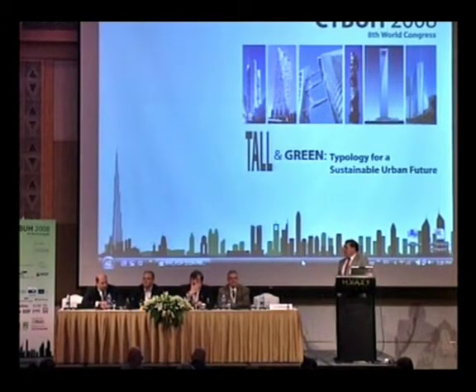So as far as the alternatives go, what I think we have to really do is take a hard look at how we design our sprinkler systems for high-rise buildings. We want to definitely make sure that the sprinkler systems have a high degree of reliability. Perhaps gravity systems or all gravity systems are a thing to consider. Maybe dual riser feeds. I know in the city of Boston, they require dual riser feeds to the sprinkler system, so somebody couldn't necessarily shut off the riser on one side and lose your supply to the floor.